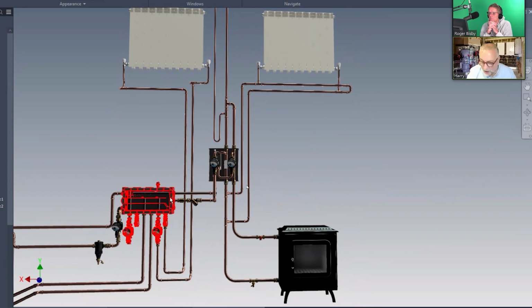And when the pump comes on at the first start, it gives a water hammer a little kick, and that'll pull something in. If there isn't a proper valve there or an appropriate type of valve, it gives a little bubble of air into the system every time. And that happens 20 times, 30 times a day. You've got a sealed system that's pulling air in, and then the automatic air vent lets it out. So it's putting air through and out and through and out. And then you open the sealed system that should be perfectly clean, and the water's all black.